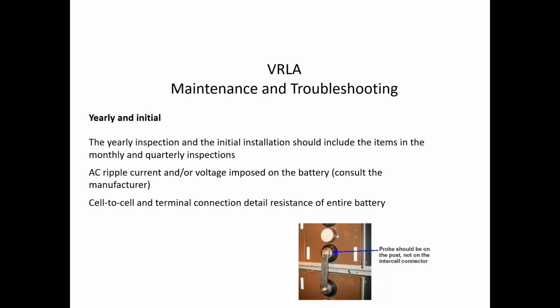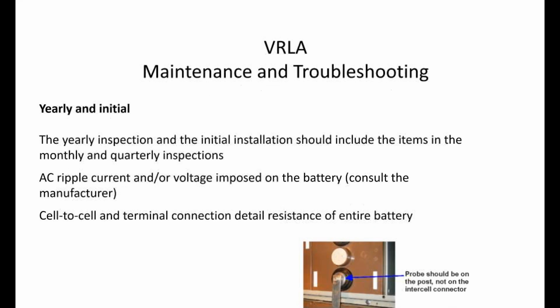Yeah, no, actually, if you look at a battery schematically, it's a capacitor, and in some real cheap and dirty utility chargers, you don't see it too much anymore, they actually use the battery as filtration for the output. And the issue with that is the battery sees those as very shallow but very frequent discharge cycles, and that can really beat up a battery. But again, that's not an issue really related to the equipment that you have installed, but it is something that IEEE recommends to be monitored yearly.